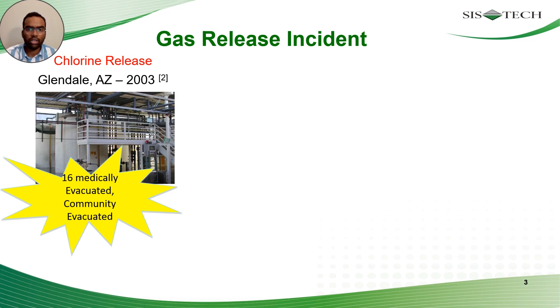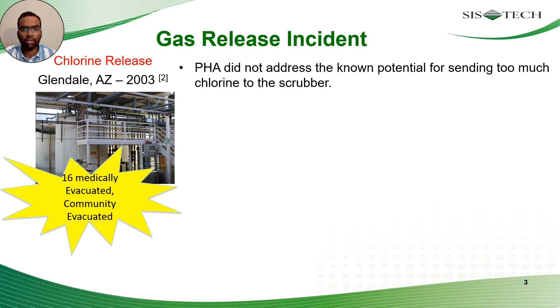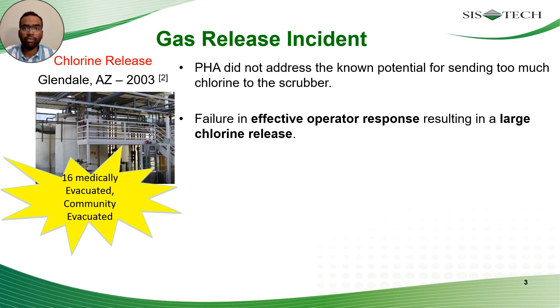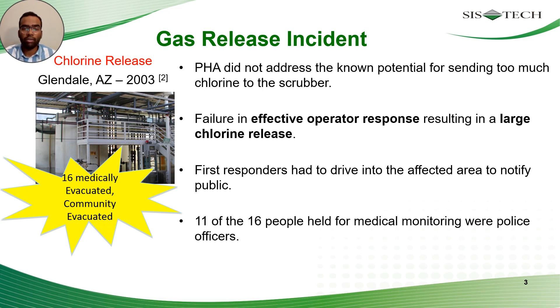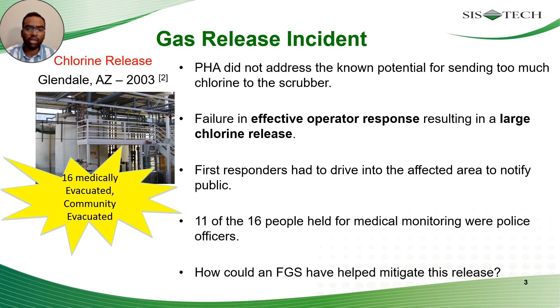Let's see what the CSB found out in this incident. First, the process hazard analysis did not address the known potential for sending too much chlorine to the scrubber. Second was the failure in effective operator response that resulted in the large chlorine release. Third, the first responders had to drive into the affected area to notify the public, and 11 of the 16 people held for medical monitoring were police officers. Could FGS have helped mitigate this release? Maybe — a gas detection system triggering an automated process shutdown and community emergency notification system might have helped reduce the severity of this incident.